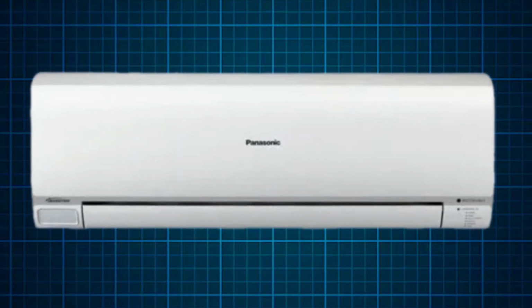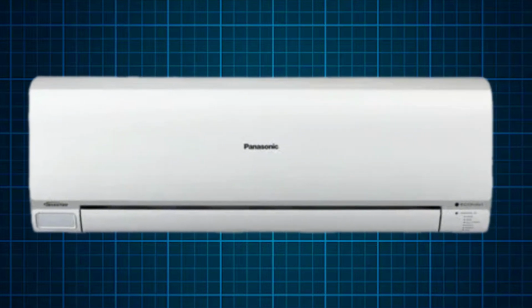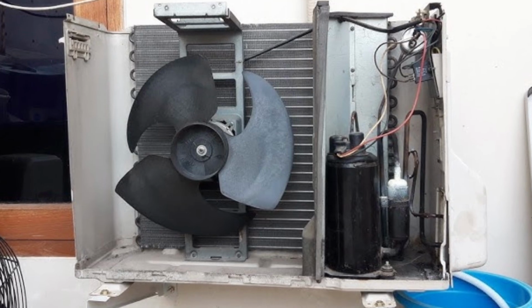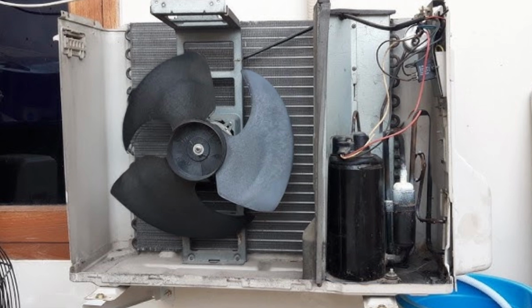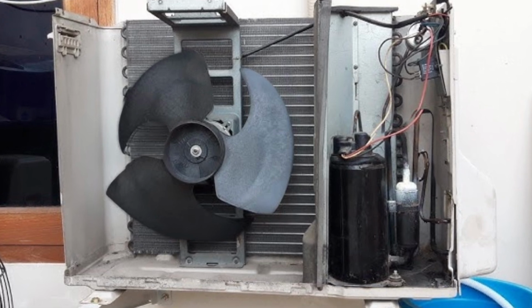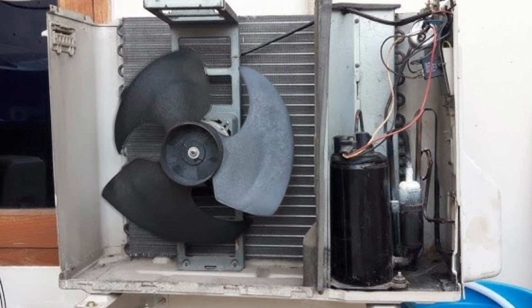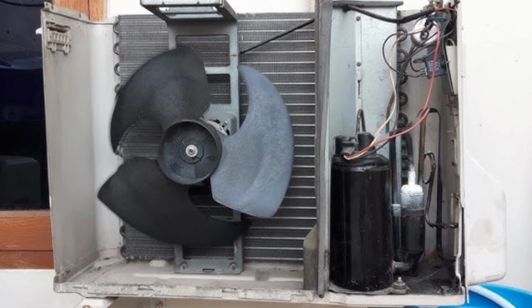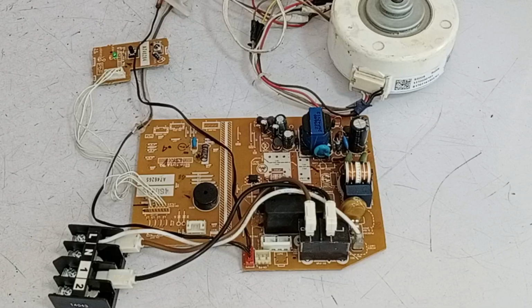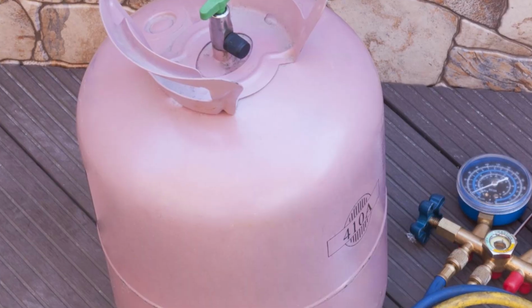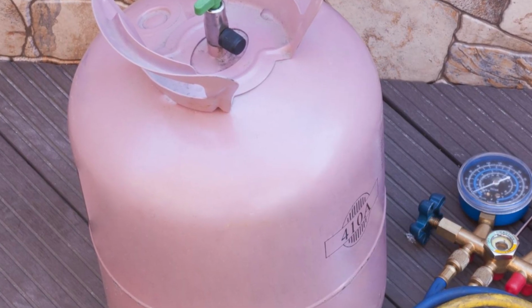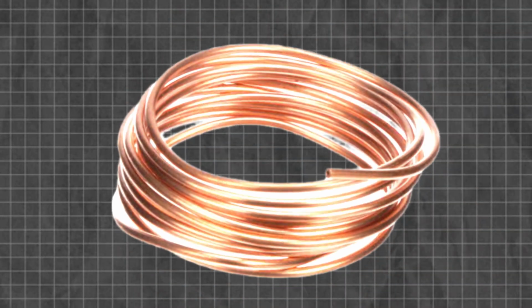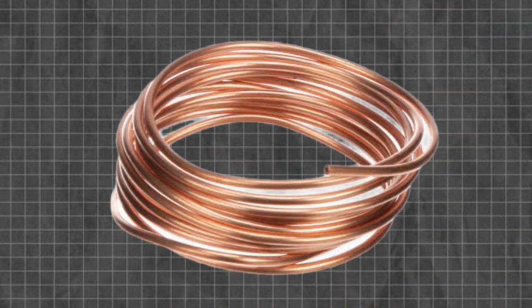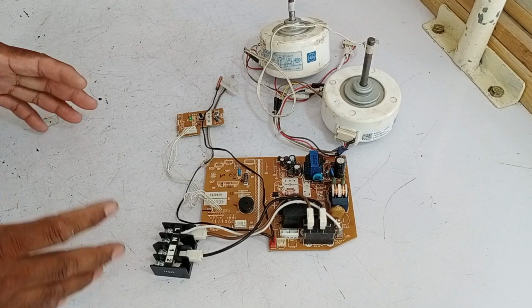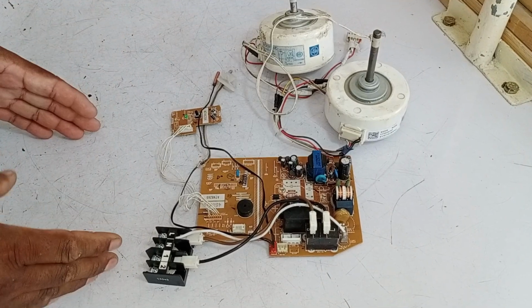To isolate the problem, you can cut off the indoor unit's power supply and directly supply power to the compressor and fan motor in the outdoor unit. Run them directly to see if they operate correctly. If they work fine with direct power, then the issue may be with the indoor unit. Another thing to keep in mind is that if the refrigerant in the unit is low, this can also cause issues. Additionally, if the capillary tube gets clogged, it can lead to problems as well. These are some of the outdoor-related issues that could be causing the problem.